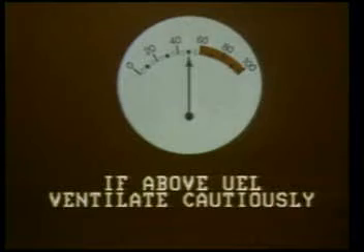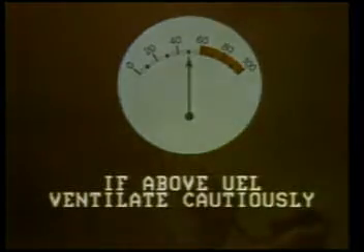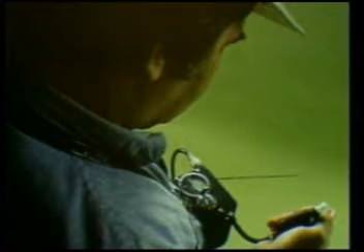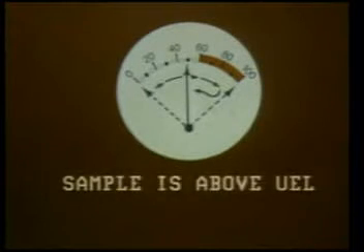into the explosive range. If you haven't watched the meter carefully or aren't sure about the reading, remove the sampling line from the area and draw fresh air through the instrument. When you retest and the meter needle moves first to the right and then to the left of the scale, it's a genuine indication that the sample is above the upper explosive limit.